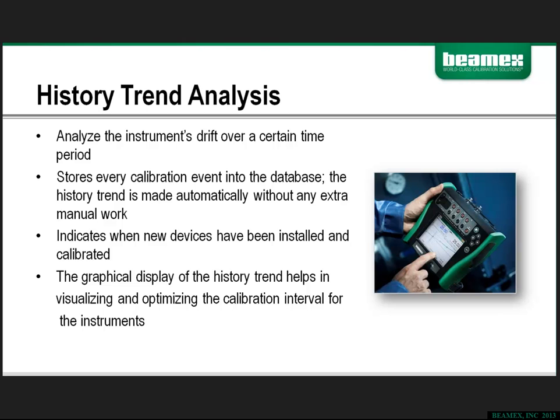What history trend analysis does is it allows the end user to look at drift over a specific period, and that can be, say, from the date that particular asset was installed into the system, or you can look at it over a shorter period of time. Say you wanted to look at the last 3 calibration cycles and see how that instrument has performed. There's a lot of flexibility, and when we do the demonstration here in a few minutes, I think it's going to be pretty clear how easy it really is to use.